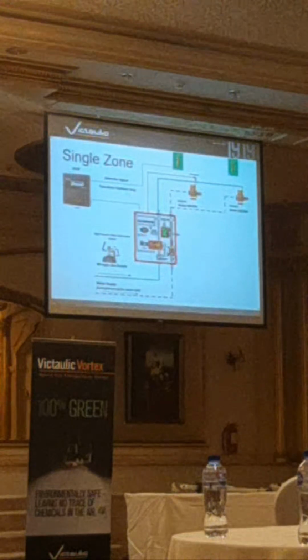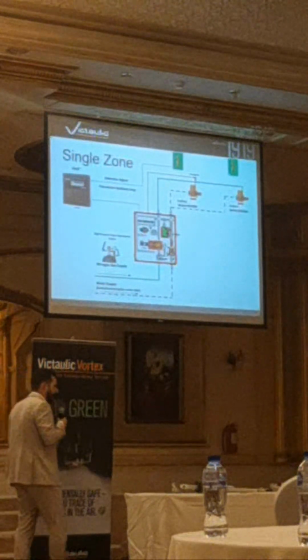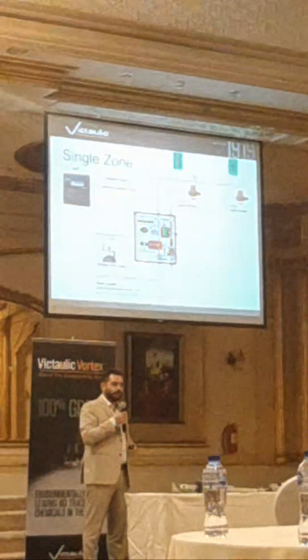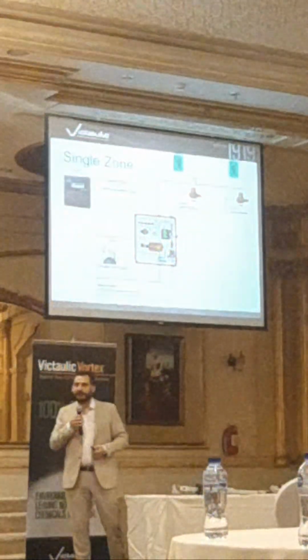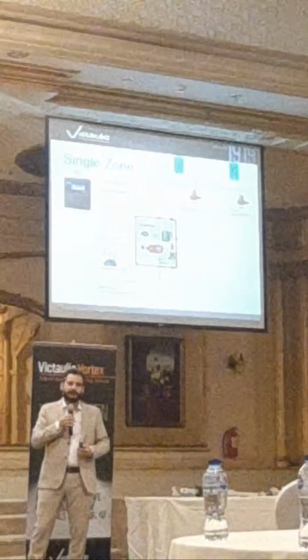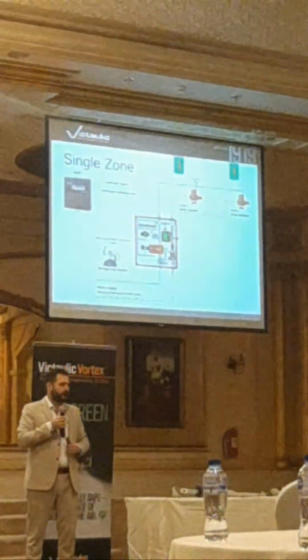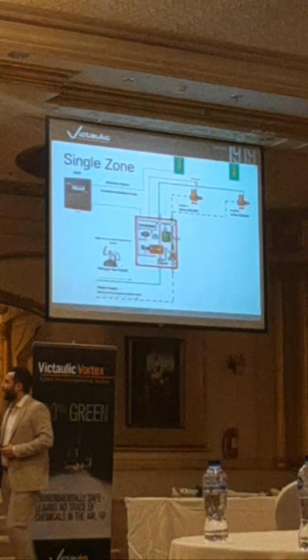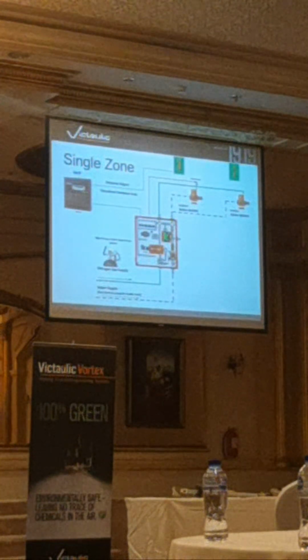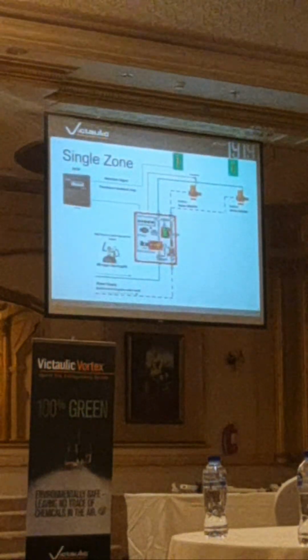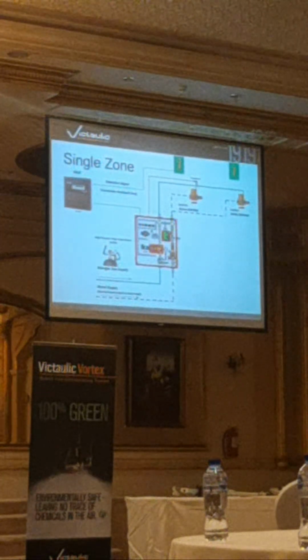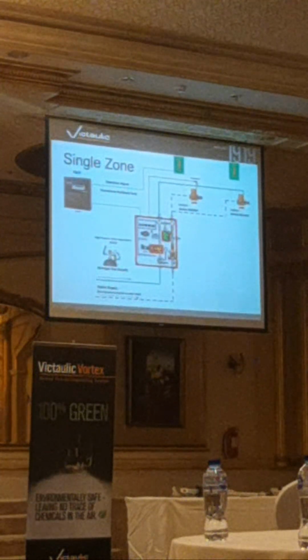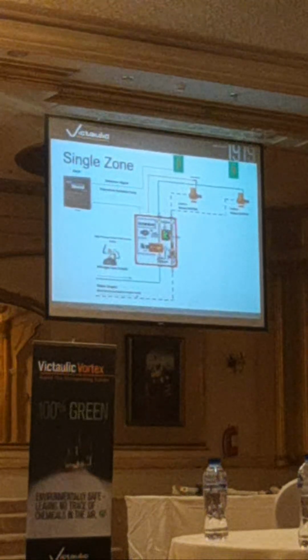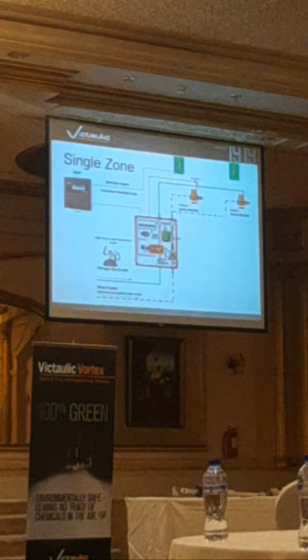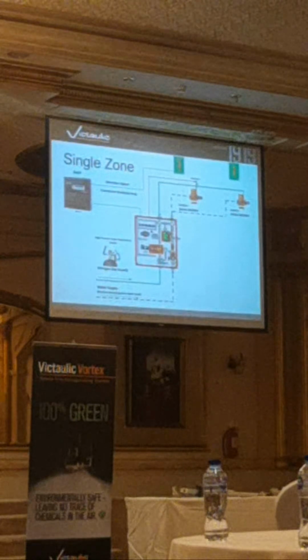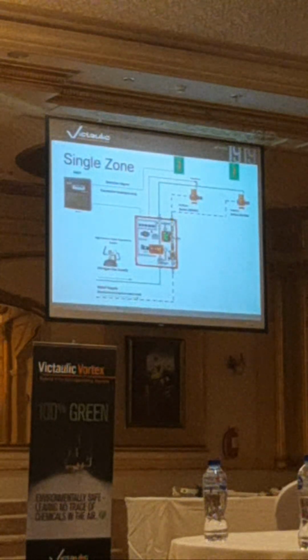Now, looking at this schematic, we're protecting a single zone, and our nitrogen supply is calculated based on the volume being protected - the more volume, the more nitrogen required. In case of a fire, your detection sends a signal to the fire alarm panel. From the fire alarm panel, a releasing signal goes to the Vortex panel, and from there you activate the nitrogen cylinders. The nitrogen cylinders, at 200 bar, run first - shown as the green line there.